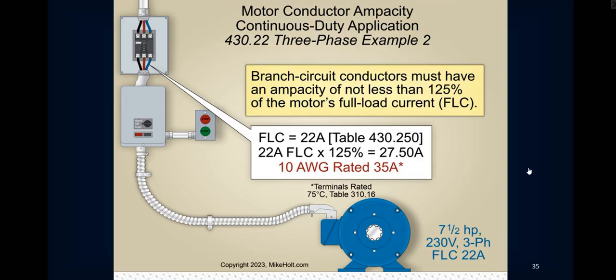Now, I believe this was a three-phase motor, so it's a 7.5 horsepower motor. And if you look across the top there, it says induction type squirrel cage and wound rotor motors. And then the voltage, what was our voltage on this one? 230 volts. So 22 amps, at 125% gives you 27.5 amps. Back to 310.16, that's going to put you at a number 10 gauge wire, which is rated at 35 amps.